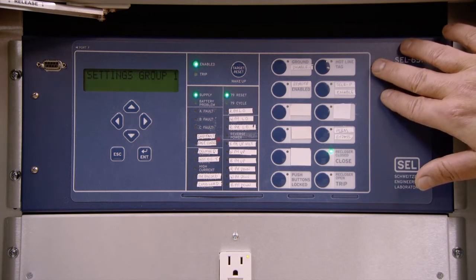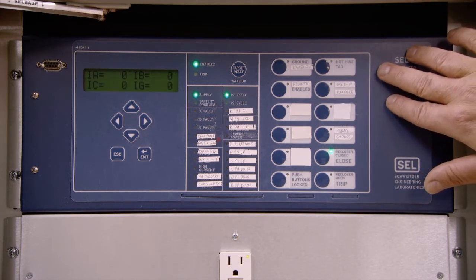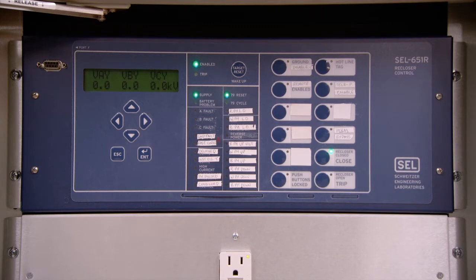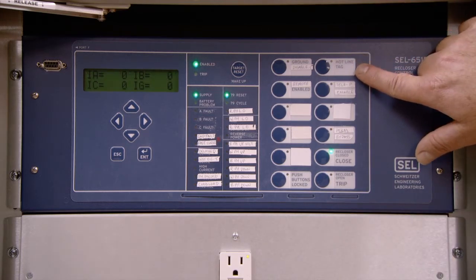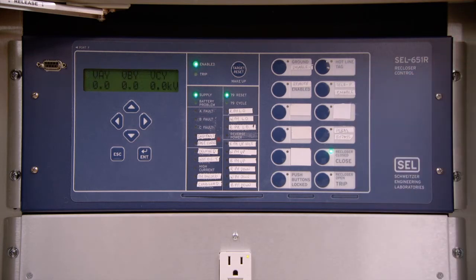Hotline tag. When the hotline tag is enabled, you will get one quick operation to lock out. So for equipment protection, when you apply the hotline tag, you will not get multiple reclosings, no matter what the unit is programmed for.